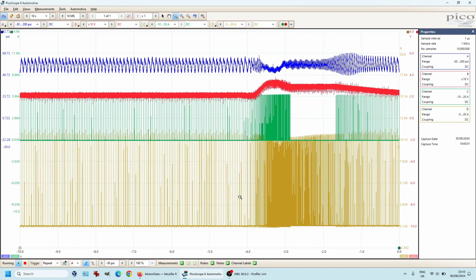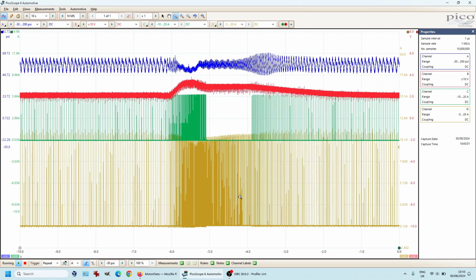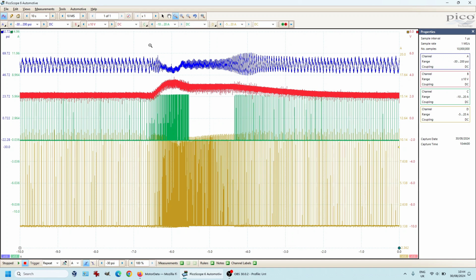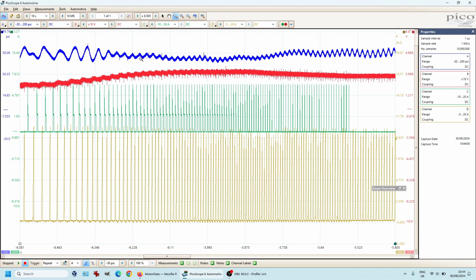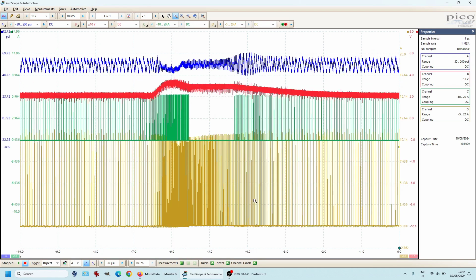There we go. And what do you see? We see a drop in pressure on our low side. When our high side is rising, our low side is dropping. That should never ever drop on a rev. It should maintain steady.